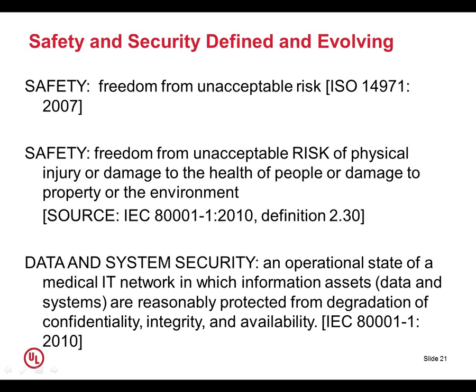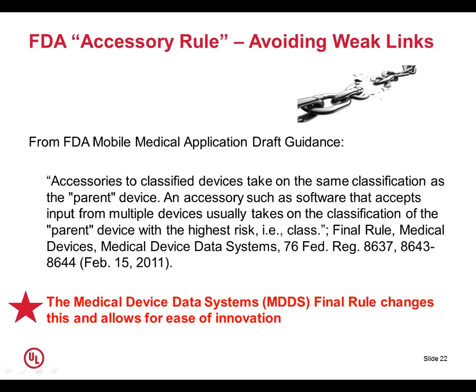And the implications of this have to do with interoperability, because if you have device A now connected to device B and device B connected to the patient, if device A can damage device B in such a way that it causes harm to the patient, now we have an interoperability related safety issue. Similarly, if you look at data and system security, we see that there are now requirements for reasonable protection from degradation of confidentiality, integrity, and availability of the system. And regulators have started to recognize this systems integration issue.